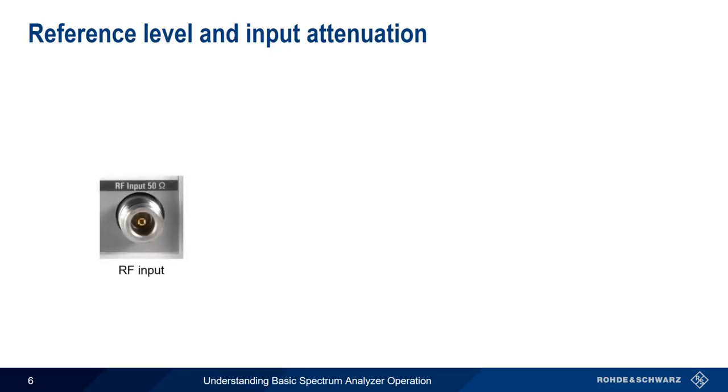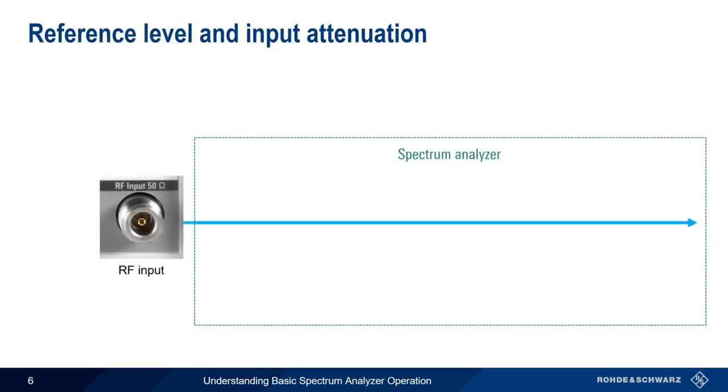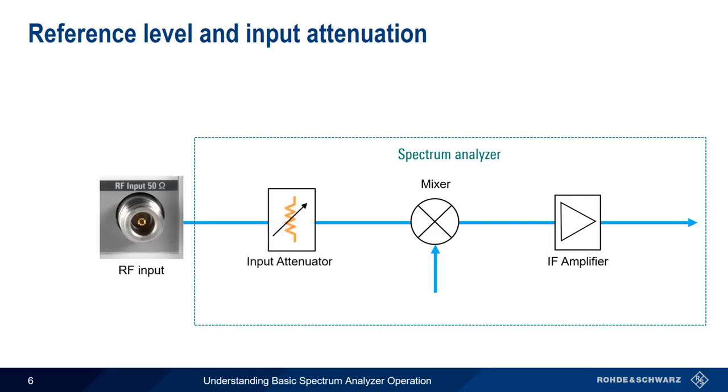Behind the RF input, some of the first sections of our spectrum analyzer include active components like mixers and amplifiers. If the input level is too high, these devices can go into something called compression, which creates distortion and negatively impacts our measurement results, sometimes very severely. To prevent this from happening, a variable input attenuator is placed between the RF input and the sensitive components. When we set the reference level, this value is used by our spectrum analyzer to adjust the input attenuation and/or the IF amplifier gain in order to avoid overloading the instrument.